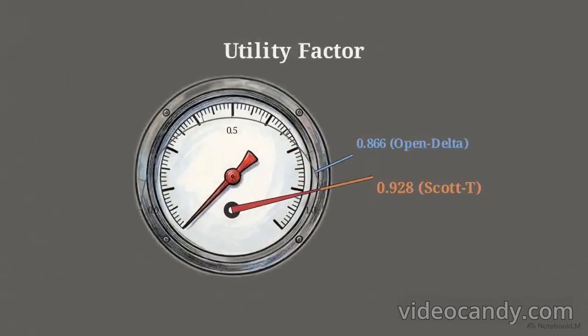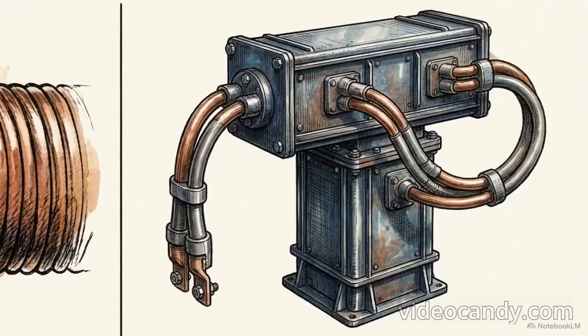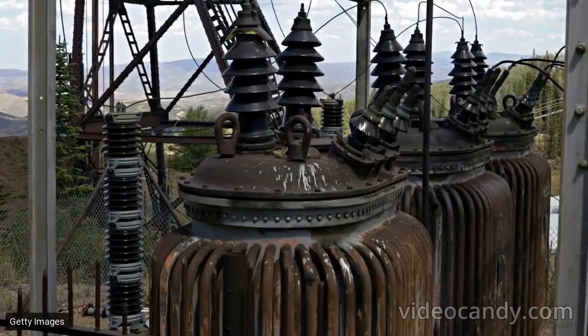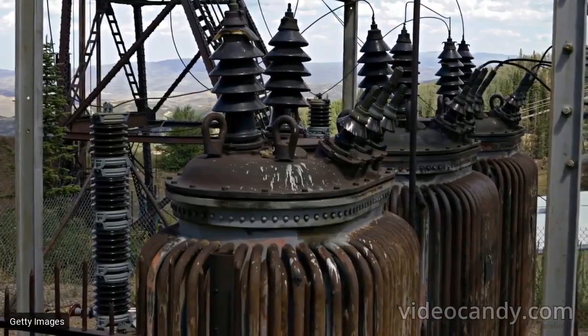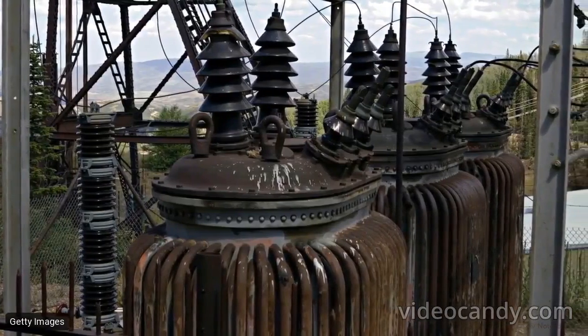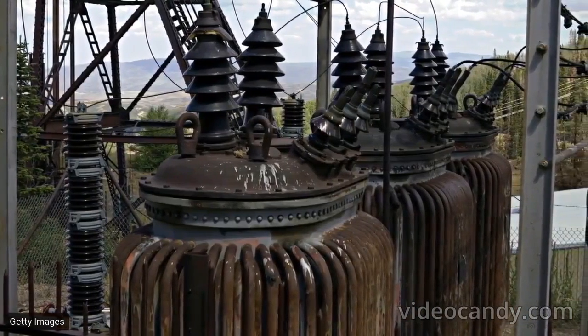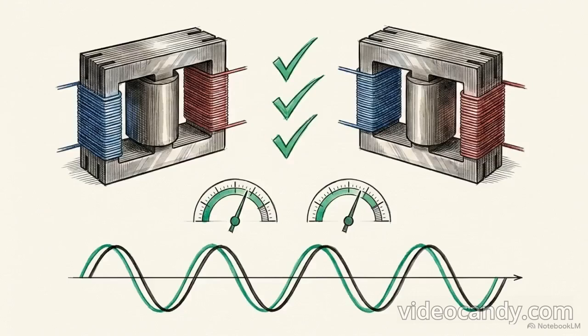Unlike the open delta emergency fallback, the Scott T is intentionally designed for high efficiency. When both transformers are operating at their designed voltage ratings, the Scott T achieves a combined utility factor of 0.928. The Scott T provides the superior geometric solution for phase dimensional shifting, extracting significantly more usable capacity from the hardware than a VV configuration ever could.